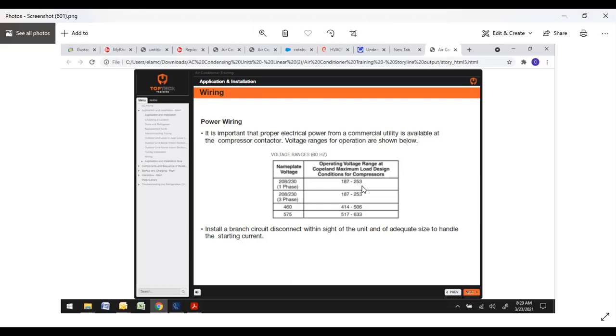What we see usually. If you start going way over 250 or higher, up around 253 or above, you will more than likely sustain some kind of damage to the unit. Especially if it's an inverter unit, the closer you get to 253, the more issues you'll have. Same with 208/230 3-phase, same voltage, 187 to 253. 460 3-phase, minimum 414, upwards of 506. 575 3-phase, minimum 517, upwards of 633.